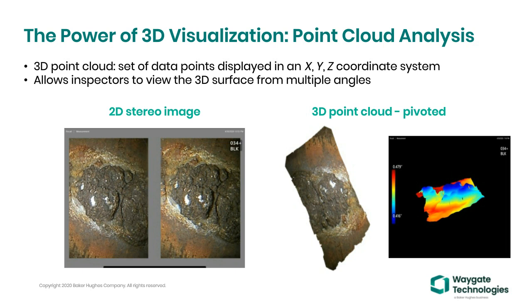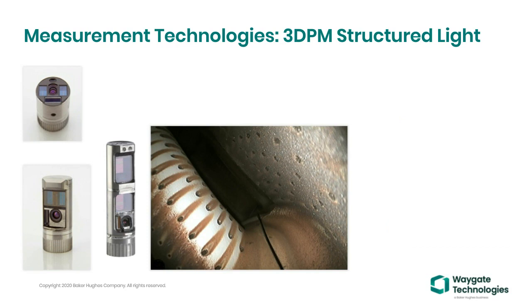Transitioning to 3D phase measuring with structured light: looking at the power turbine blade image, you'll notice it is a wide 105-degree field of view from the corners diagonally—not a split image. You go in, inspect, and get measurements on demand with various optical tip adapters—forward view or side view. Recently, a far-focusing and farther-measuring side view tip was released. You can see fringe pattern generators above the optical imager—when capturing a 3D image, those fringe pattern generators fire sequentially and generate a series of fringe patterns or shadows onto the targets.